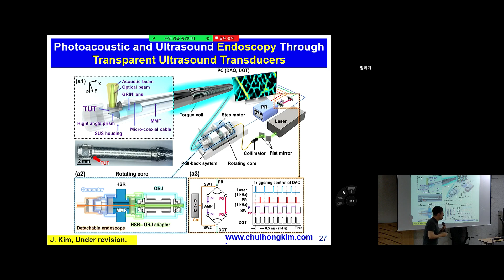But the problem is, since they need to put the optical excitation source and acoustic detector in small size, the efficiency is no good. They lose the performance in optical. They lose the performance in ultrasound. However, if you use the technology in the clinic, you need to maintain each technology's performance like 100%. So that's why we use a transparent transducer. It's very sensitive, and then we make the endoscopy about 2.3 millimeters. So this size of the probe is perfectly matched to the commercial Olympus endoscopy system instrumentation channel.